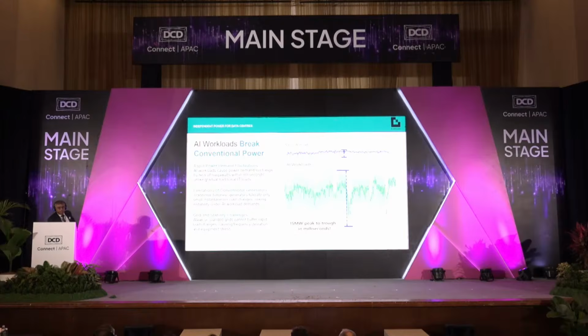As you can see there, the two graphs. One is the non-AI workloads. Non-AI workloads is very stable, with very little deviation and oscillation from the maximum capacity, whereas the AI workloads have a huge oscillation and huge difference, tens of megawatt of power that oscillates in a few milliseconds time. That's the first problem, fluctuation in power demand.